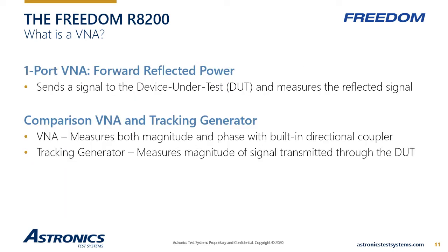The Freedom R8200 VNA is a one-port VNA. The instrument generates a sweeping signal into the device under test, or DUT, and measures the magnitude and phase of the reflected signal. The magnitude measurements are displayed as return loss or voltage standing wave ratio, which are the most common LMR measurements. Phase will be displayed in degrees and also visualized on the Smith chart.